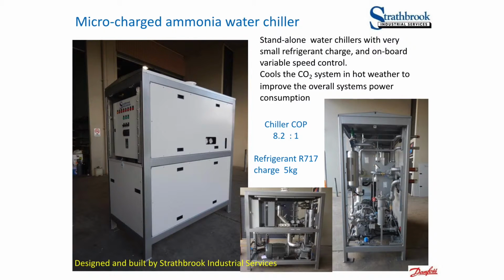The machines are about the size of a big wardrobe. It has a single compressor in it with a VSD. It's doing about 170 kilowatts of cooling with a COP of 8:1, which is pretty good, and it has 5 kilograms of ammonia in it. It's sitting outside, so if it dumped the entire gas charge, by the time it got 500 metres away, not too many people are going to know about it.